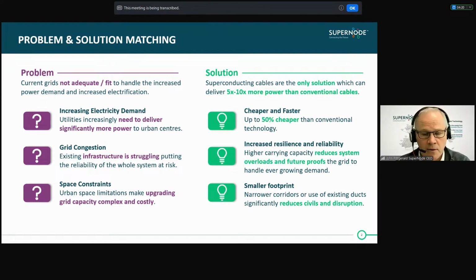There's a use case later which I'll talk to, but they're certainly faster. They don't generate heat, so they can go in existing corridors and existing ducts, reducing the civils, the substation work, and the disruption and time required to deliver grid as required. When this grid is in place, we're talking about greater resilience and reliability, because if you need 3 times the power transfer capability and a superconductor can give you 5 to 10, that's headroom, that's resilience in your system, in your network, and it future-proofs you against future needs that happen very quickly.